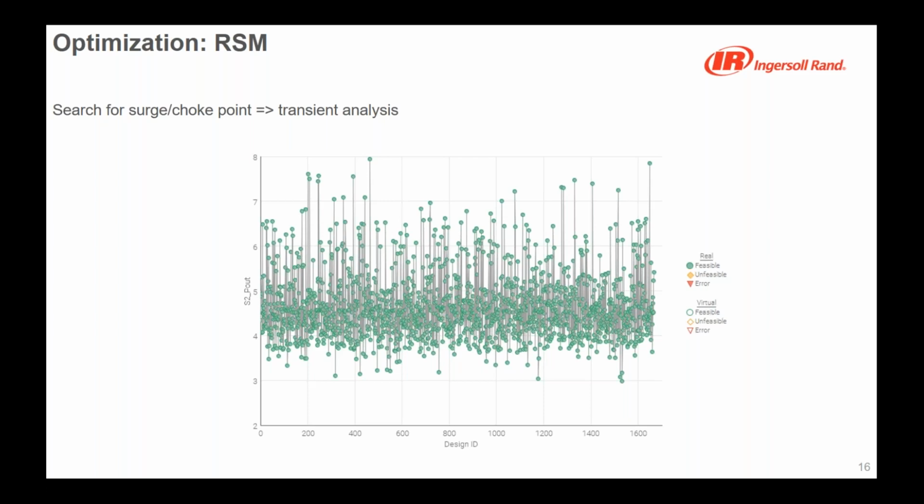Why look into that? We have a 2-stage machine, and one of the ideas was, I know that my machine will surge, and you typically look for surge only at the design point, but we had a broader ambition.